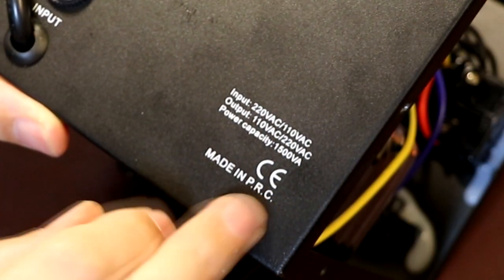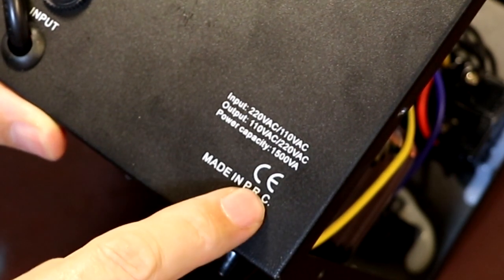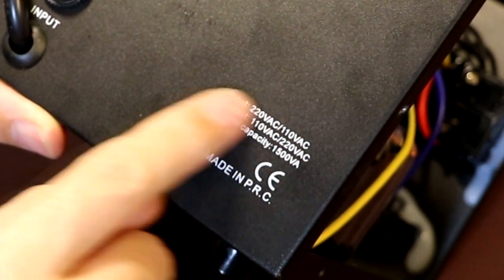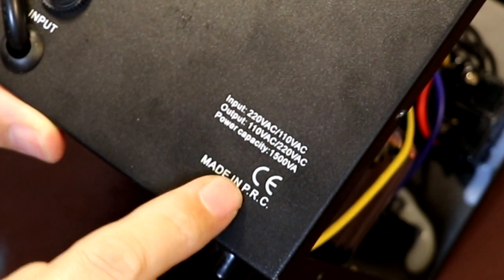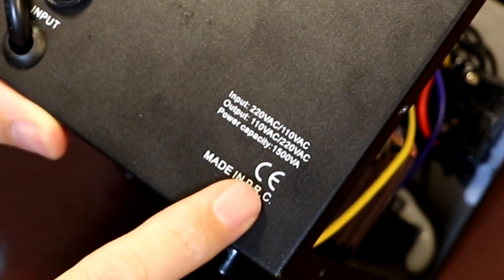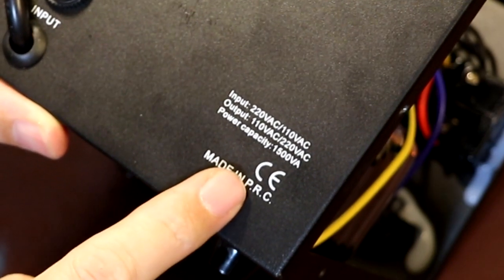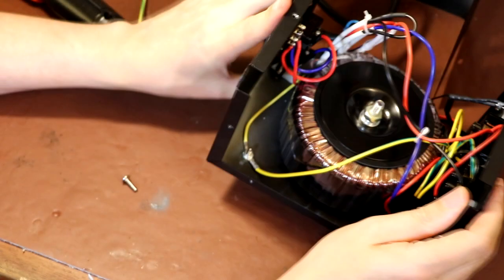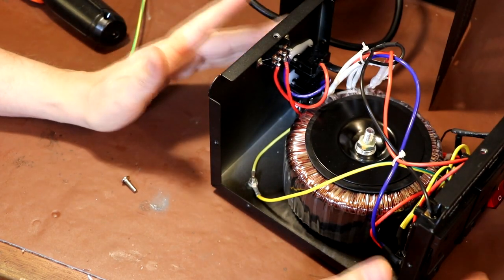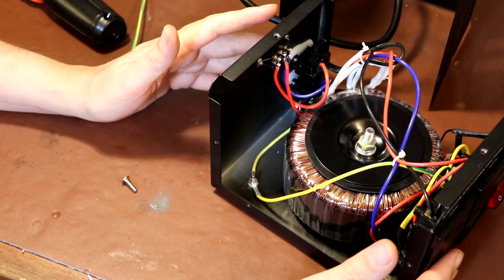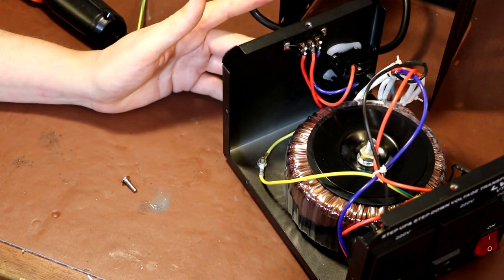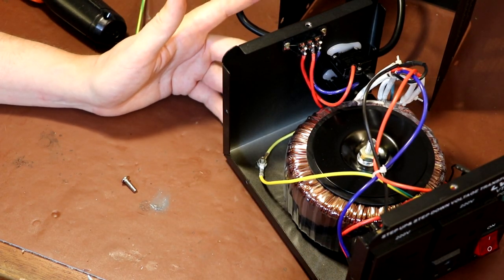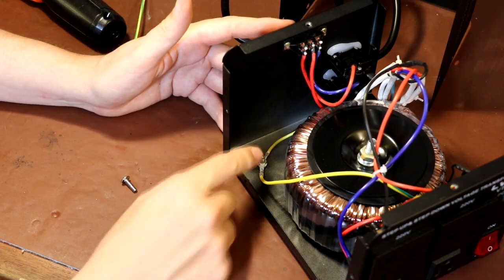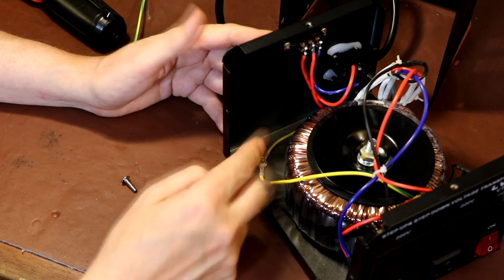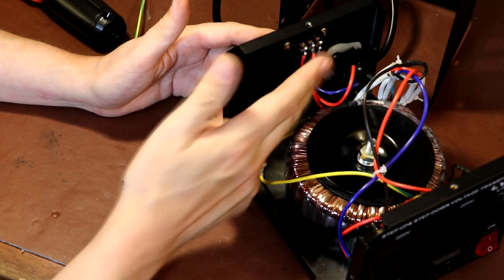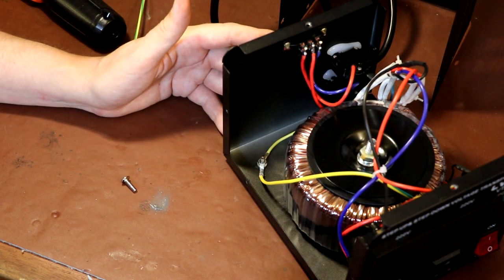Looking at the back of this transformer, you can see it's got this CE mark, although some people say that stands for China Engineering, but what they're trying to say is it's CE marked. If it's CE marked, it should be safe and comply with the appropriate electrical standards. Well, just looking at it, I'm 100% sure it doesn't comply with the electrical standards, certainly not for today. Now, would I still use this piece of equipment? Yes, I would, because I've got enough knowledge to keep myself safe. But the fact that it's not earthed correctly here, and perhaps some of these exposed terminals, the risk posed by this just doesn't comply with the standards.